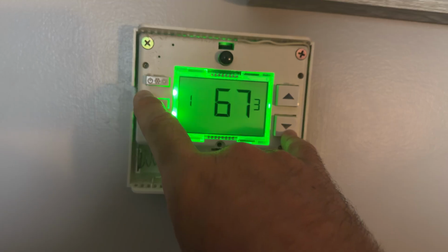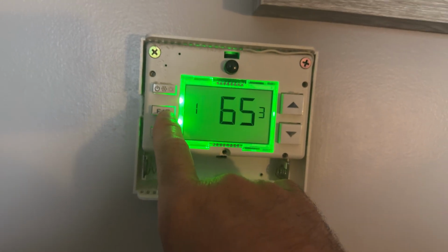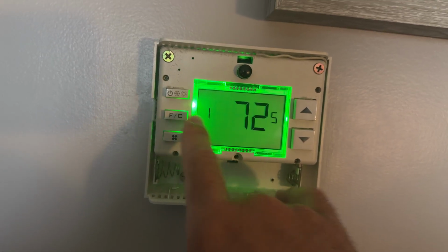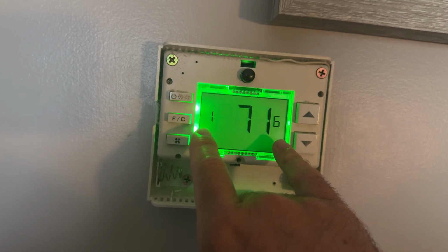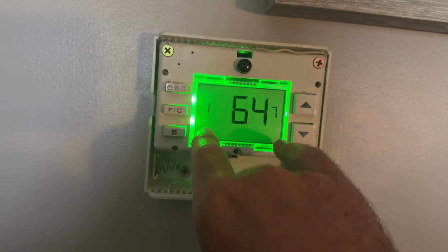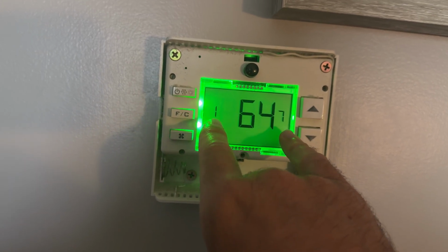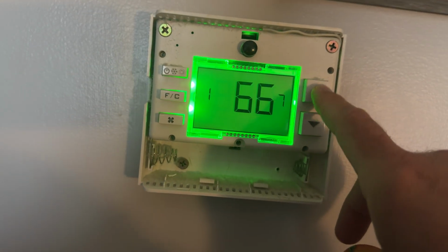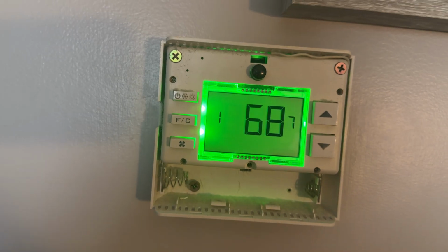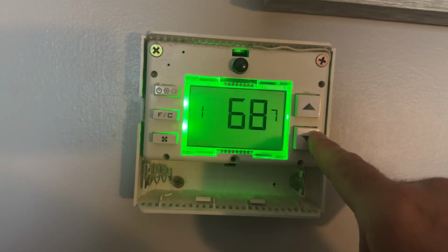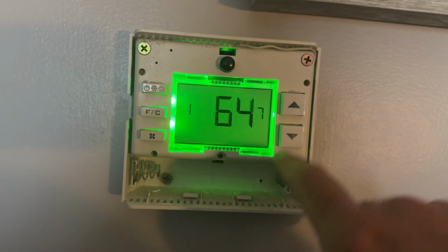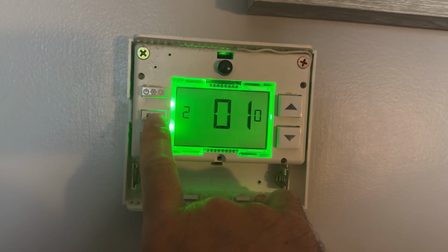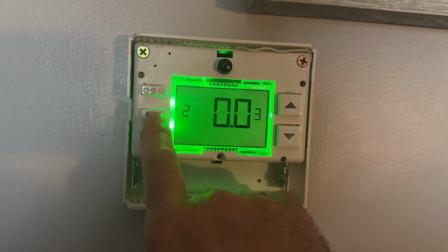And then this is something, this one doesn't matter. This is like a range between plus or minus. What you want to get to is the 1 and a 6, or 7 rather. 1 and 7. This is the lowest temperature that the guest is allowed to operate. So before it was set to 68 and we couldn't go any lower. So 1, 7 is where you can adjust how low you can set it. And then we'll go forward, and that should be all you need.